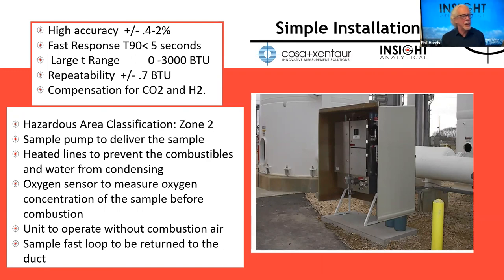High accuracy. We can typically get somewhere between 0.4 and 2%, depending on how much variability is in the composition. And again, going back to Lee's question earlier about how much variability there is in things like hydrogen, we've got to really make sure. And so we have a whole tool that we use to try to figure out what the optimum calibration standards are for a given expected range of process fluids we're going to burn.